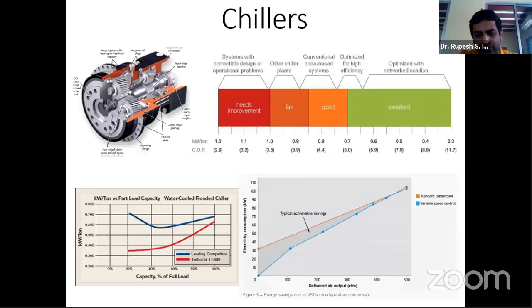So again, chillers, I think there was a mention that we have gone from a COP of almost 2 or 2.5 with the classic window air conditioners, which were there not very long ago, to about 8 COP. And nowadays, with the process also coming into play, which can be a water side process, the HVAC plant efficiency could be as high as 12. So COP of 12 probably 20 years ago was unheard of, and probably nobody could even believe that we could actually cross a COP of 10 on the HVAC side. But today, I think technology has developed very quickly, and we have moved towards these higher COPs, and 12 is also achievable today in the context of zero energy buildings.